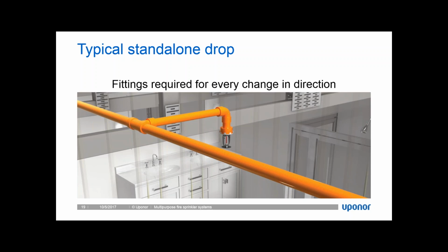When I say dry fit, what I mean is I can put the pipe inside that fitting without adding any glue to it. When I've got it installed like that, it looks like the connection is made, although the connection might not be made. And I may forget about dry fitting that fitting. And then later on, when I go to test the system, the fitting will blow off and I'll get water everywhere. This doesn't happen on most job sites, but it's happened to most contractors where they've had a fitting that wasn't glued and it blew off either before the sheetrock was up or after the building was finished. And that really digs into the bottom line and it ruins a lot of material in the building.